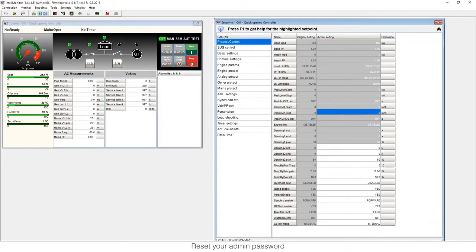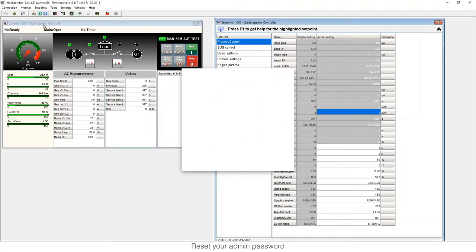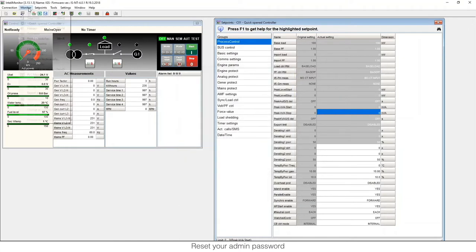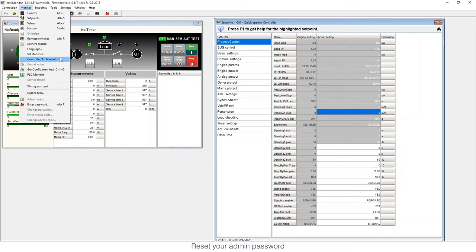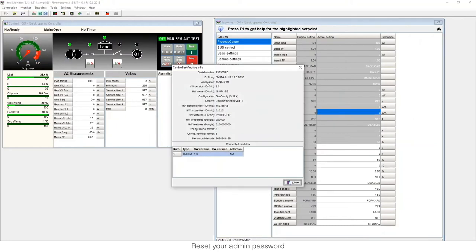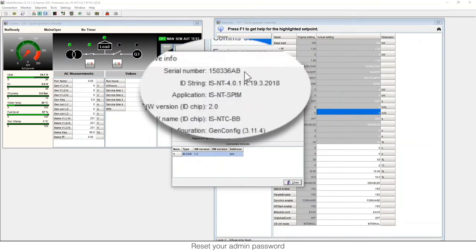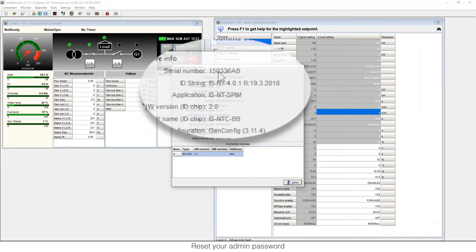To reset our password, we need to go to the ComAp website and use our friend IntelliBot that will help us during the process. He will ask us for some information that can be found in Monitor Controller Archive Info. This information is the serial number that can also be checked in the physical controller. Monitor Controller Archive Info, and there you can see the serial number that we're going to need during the process.